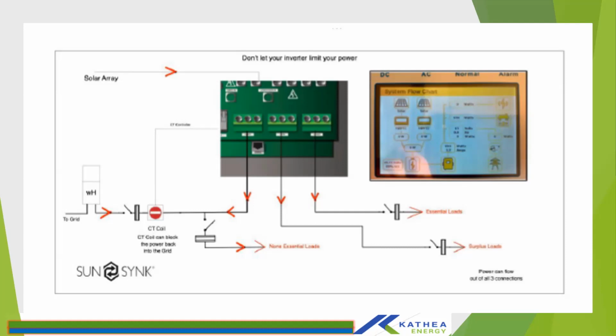So your CT meter has to be installed right after the mains breaker, before supplying anything to the house. That's where you should clamp your CT, so that it will be able to monitor both your critical and non-critical loads. Soon after your main incomer from the grid, it passes through the municipality meter and then to the mains breaker. Soon out of the mains breaker, that's where you need to hook up your CT and wire it to the inverter. So I usually recommend that when you are siting a place to install the inverter, try and find a place which is closer to the main DB, such that you can cut the distance short between your CT and your inverter.